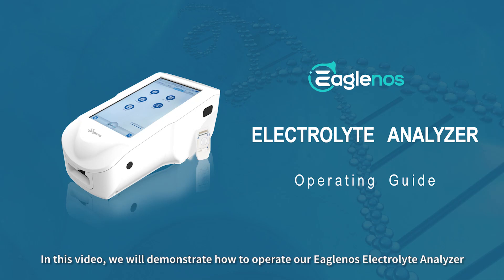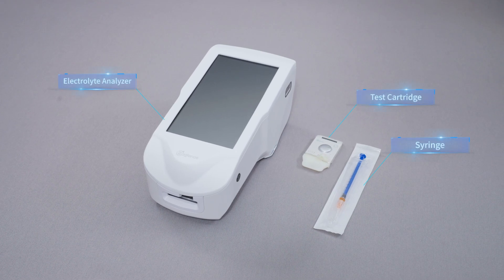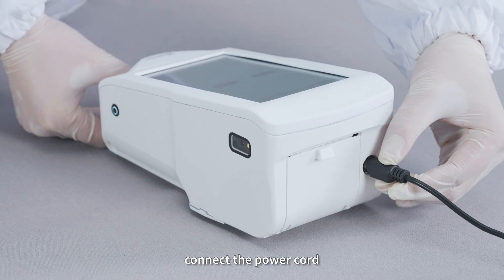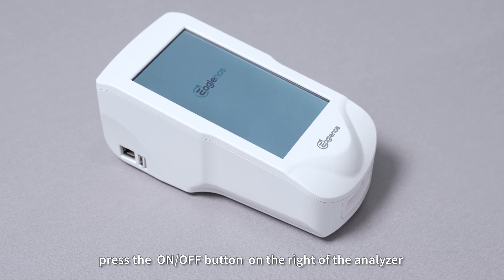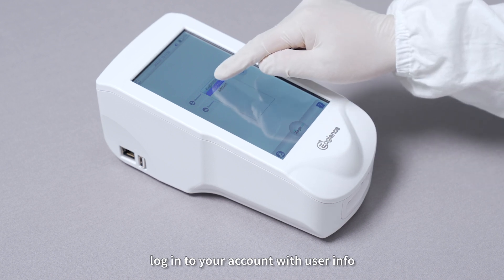In this video, we will demonstrate how to operate our Eaglenos Electrolyte Analyzer. Connect the power cord. Step 1: User Login. Press the ON-OFF button on the right of the analyzer to turn on the analyzer. Login to your account with user info.